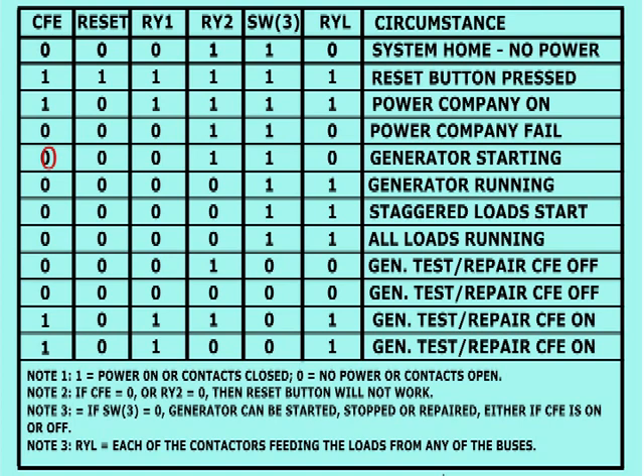The next step is to manually start the power generator. When the generator is running, it starts generating AC power, so the RY2 relay, whose contacts were closed up to now, delivers a 0, disabling the reset button, so that it is not possible to close and interlock the RY1 contactor again, thus avoiding a short circuit of the generator with the power grid. When there is 220-volt alternating current voltage being delivered to the generator bus, the staggered loads begin to turn on, one by one, according to the time set by their corresponding time delay relays. Eventually, all the loads will be running, so they all are turned on and running on the generator AC.